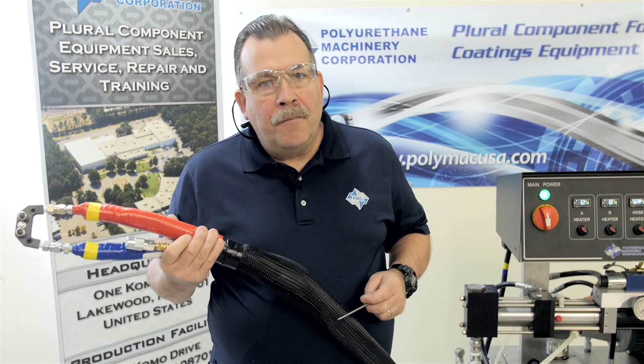Before we go into a manual override on our controllers, we want to put a thermometer into the end of the whip. We need to do this in order to know what the temperature is of the fluid within the hose, because we can no longer see that since we have a sensor signal break.